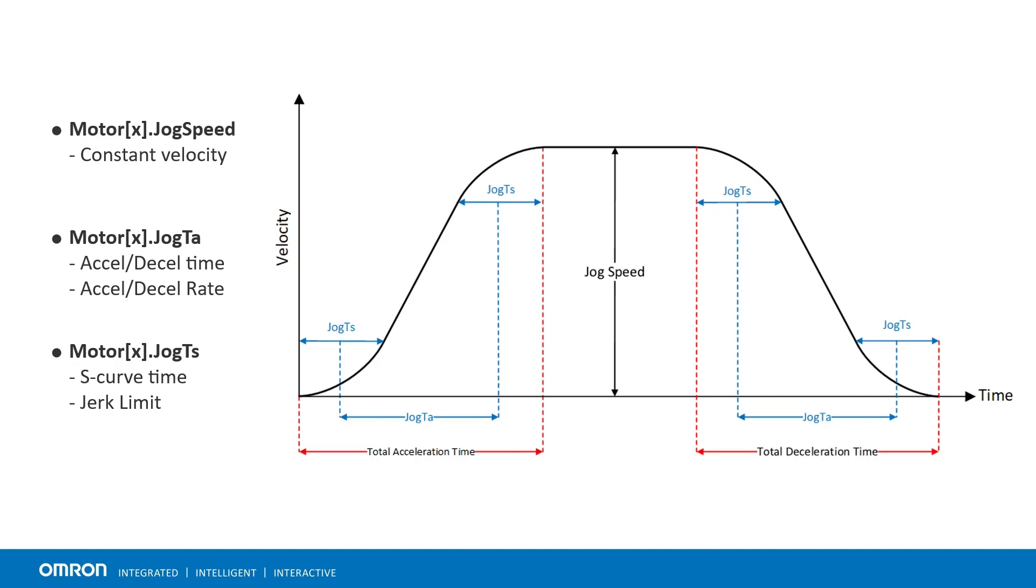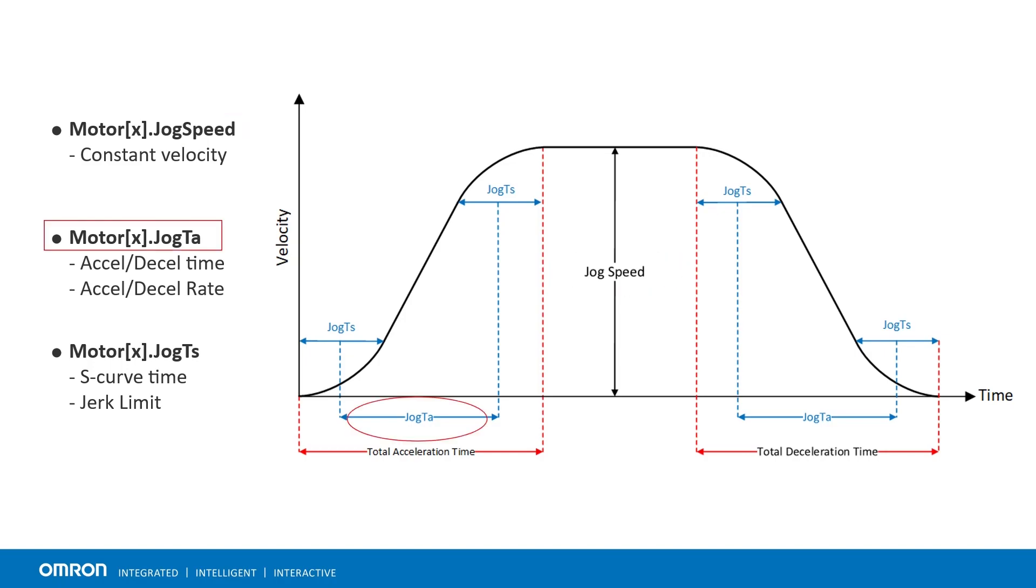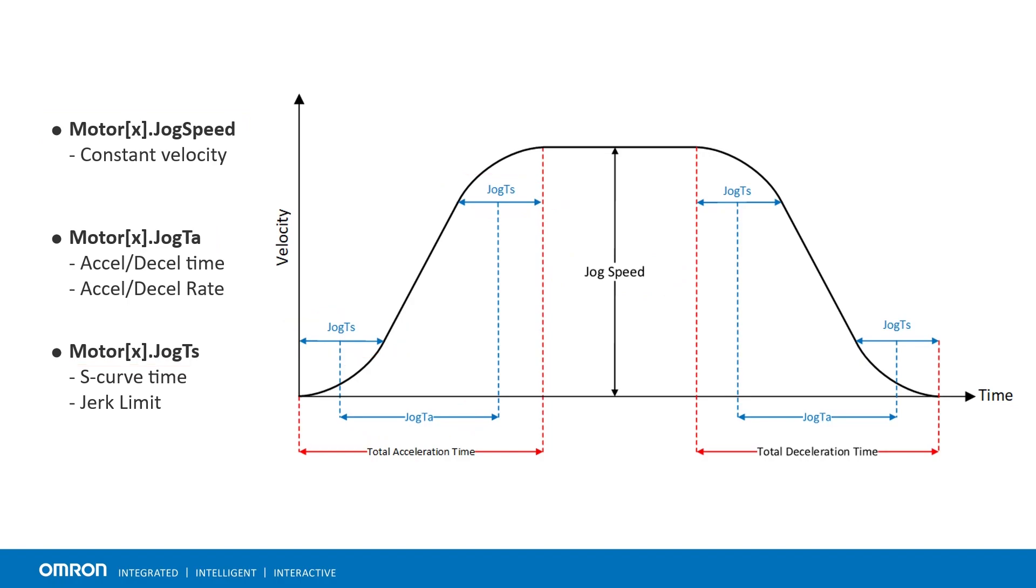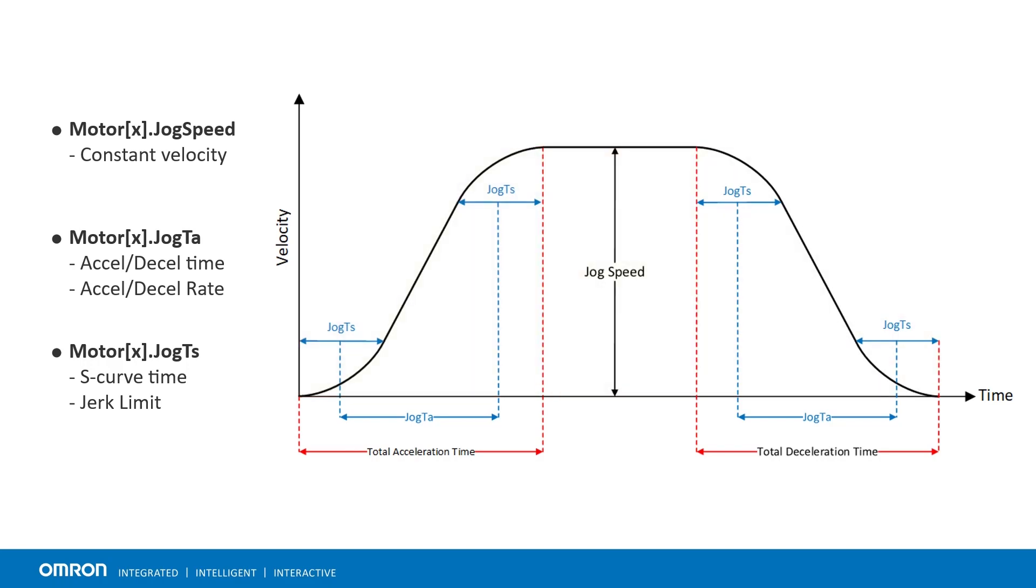Jog moves are trapezoidal velocity versus time profiles. They are programmed using three essential motor structure elements: jog speed, jog TA, and jog TS. A jog move profile consists of three portions: an acceleration, a constant velocity, and a deceleration. Jog speed specifies the magnitude of the constant velocity portion, whereas jog TA and jog TS specify the shape of the acceleration and deceleration portions.